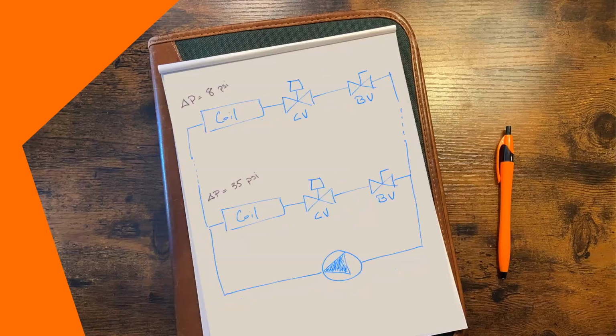So if we redraw this model so that now we have the included manual balancing valves. In this configuration, the far zone is under control, as it was with no balancing valve, and that close zone is balanced at full flow, but is unprotected from pressure fluctuations and will experience the effects of poor valve authority as flow decreases.